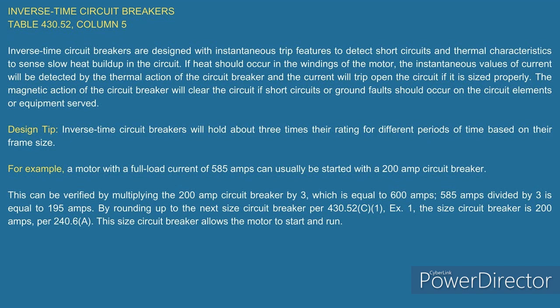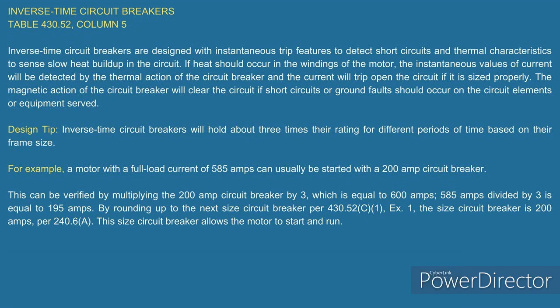Yeah, absolutely. And I'm not really technically agreeing with you, Juan, on using the fuses as an inrush overcurrent protection device, or just to use a control transformer. Not really sure what you mean by that, but it just depends on what you're trying to do. If you're using this math that they have in here, you have to have those fuses set a certain way, or you're just gonna pop the fuse every time. So it depends on what you're doing. If you're trying to protect the equipment from damage, then you're gonna want to have that dialed in because you don't want an unintentional rapid disassembly in the field.